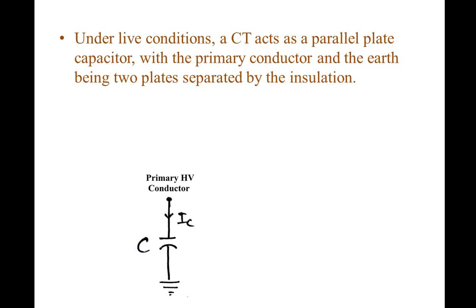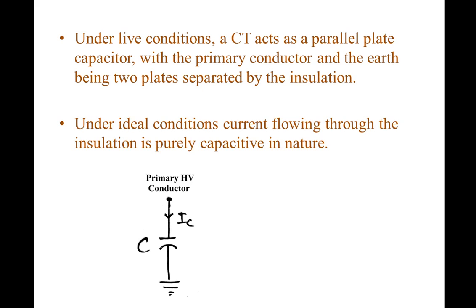Under live conditions, a CT acts as a parallel plate capacitor, with the primary conductor of the CT and the earth connection being two plates separated by the insulation. Under ideal conditions, the current flowing through the insulation is purely capacitive in nature. Therefore, as shown in this figure, the current IC leads the applied voltage by 90 degrees.